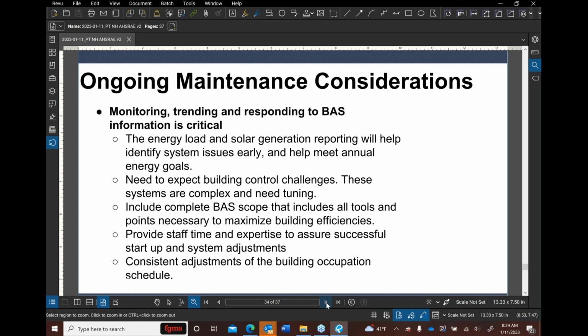So another thing to consider is that really paying attention to what the BAS system is telling you is going to be really critical. Your clients or operators will need to be paying attention. And really, I would say, Jeff can comment on this, but IMEG has had to pay much closer attention to what the BAS system is telling us than they would typically do, because that was how we managed to catch, as Jeff mentioned, that the resistance heaters were running in the first 2 months.